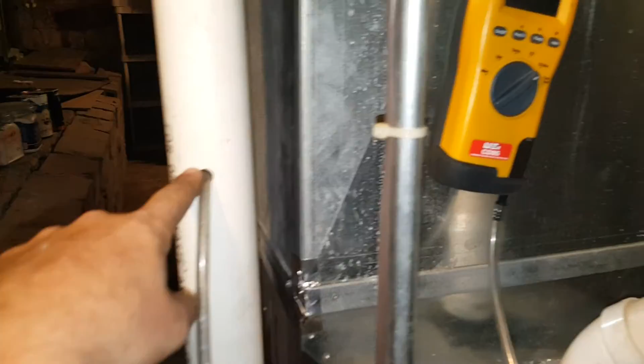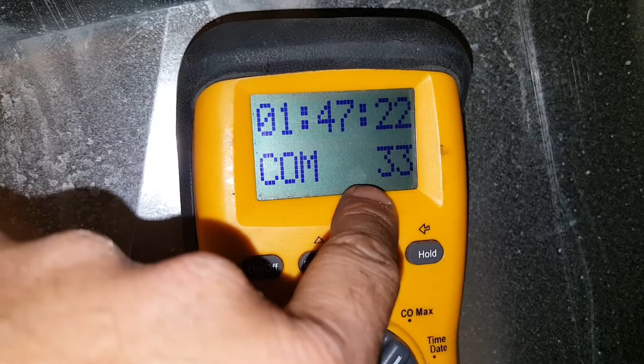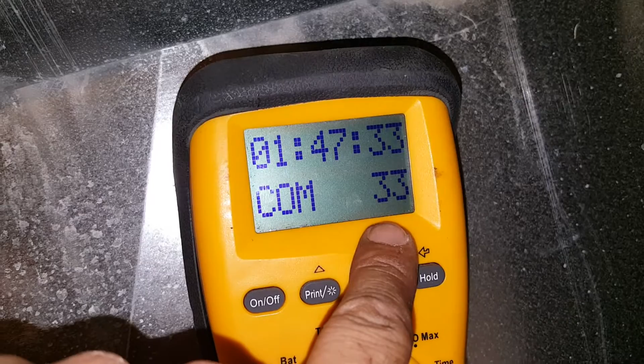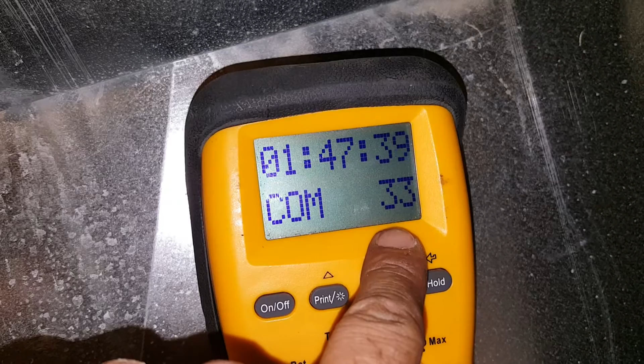And we are taking a carbon monoxide reading: 33 parts per million in the chimney, leaving the house. I'll sign off on that. I follow Mid-America's guideline - 100 parts per million in the chimney is too much, 33 parts per million is okay, you're safe. We'll sign off, call it good, and wish these guys the best of luck with their furnace.